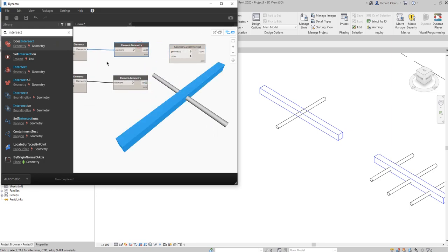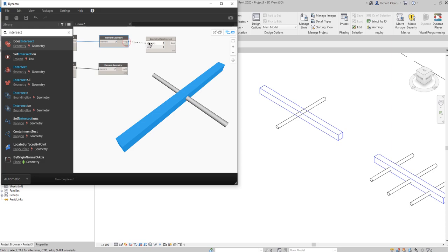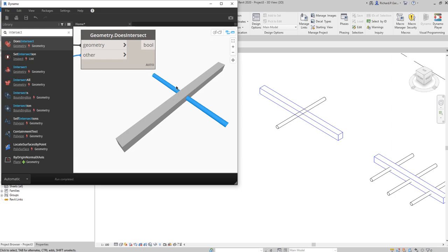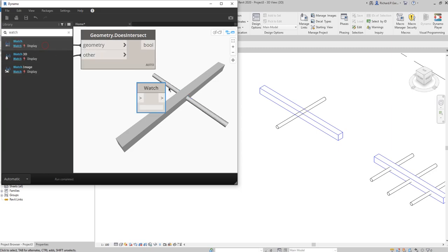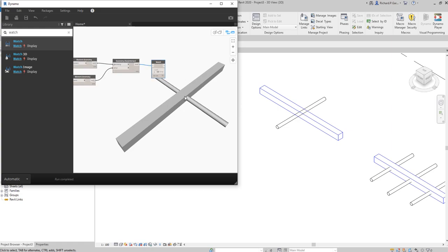Select the DoesIntersect node. You have two inputs — one for the pipe and one for the duct. Connect them. If you hover over the output you'll see the Boolean result, which is 'true' — meaning they are intersecting. I'll also add a Watch node so I don't have to hover. We have one result: true. There is an intersection between this duct and pipe.